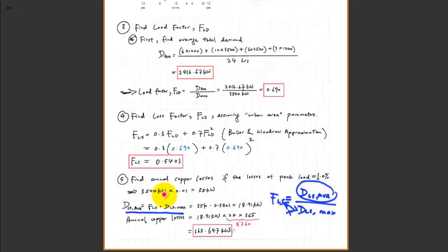Make sure you understand the question accurately — it asks for annual copper losses. Annual is the key. There are 24 hours times 365 days, giving the magic number 8760 hours per year. Multiplying 8760 by 18.91 kilowatts gives you the annual copper losses, which is 165,647 kilowatt-hours.